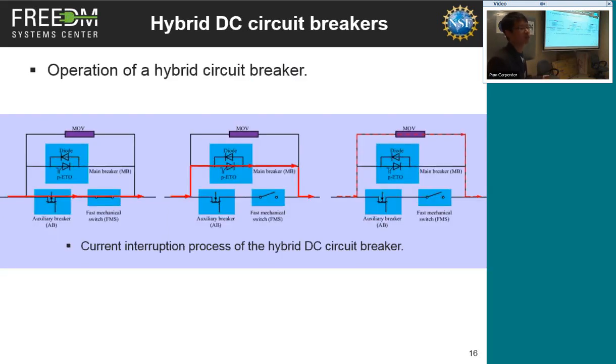But before that, maybe we wonder why we need a fast mechanical switch. So let's look at how a hybrid circuit breaker works. First, you have the current flowing into your mechanical switch, and then you want to transfer it to your semiconductor switch here. Then you want to turn off your semiconductors so the current goes into the MOV. And at that moment, the voltage is really high. You turn off your semiconductor, which takes a few microseconds. At that moment, the mechanical switch, as well as the semiconductor, should be able to withstand the voltage. The voltage will rise very quickly, so it doesn't give you much time for further opening. So at that moment, you should have a gap between your mechanical switch contacts that is able to withstand the voltage.